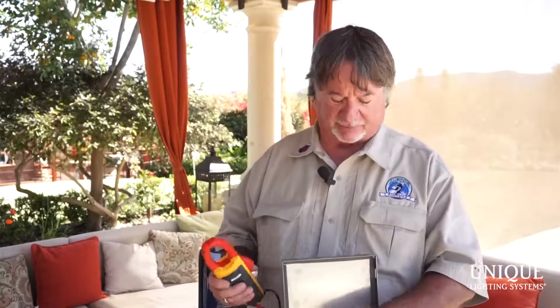Now the second thing I'm going to do is take my run number 9. I'm going to move the dial from my amp probe to amp squiggly line, so that's amps alternating current. What's an amp? I don't even care what an amp is. You're going to buy an RMS amp probe meter and just look and read what the dial says. So you take the jaws and put them around either one of the wires.